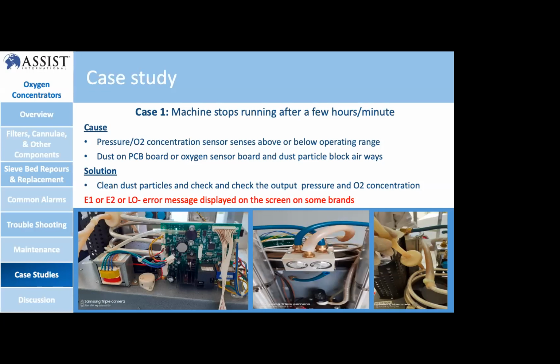The other cause is dust on electronic components, that means on the PCB board, an oxygen sensor board, or dust particle blockage in the airway. So those are causes for these cases. That means this causes the machine to stop after a while, or after it runs for a few minutes.